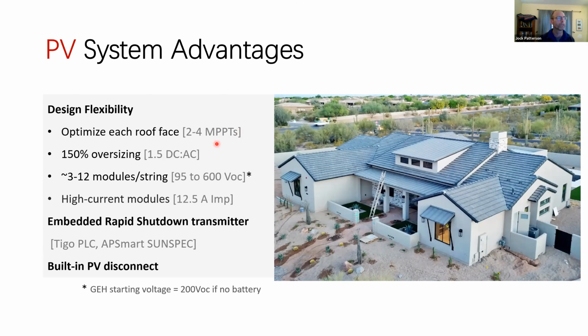Each string will be optimized because there are up to 4 MPPTs, so you can do 4 roof faces. In the residential world, it's unusual to go beyond 4 roof faces. So generally, you're always optimizing each string. And if you have little or no shade, then there's no need for an optimizer. That's all done within the string inverter. You can also oversize to 150%. Very useful if you're doing east-west roofing, right? You're only getting half the system exposed to the sun in the morning and late afternoon. So it's great to be able to do oversizing.